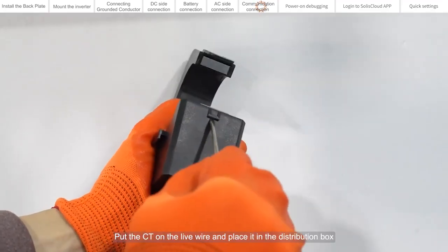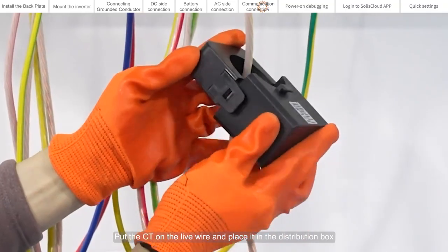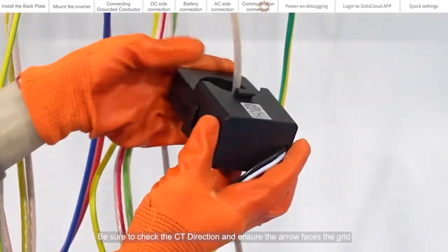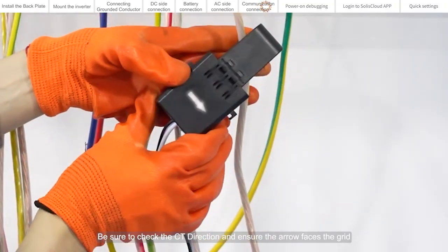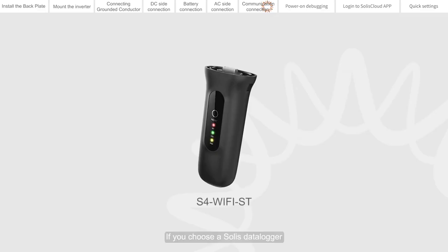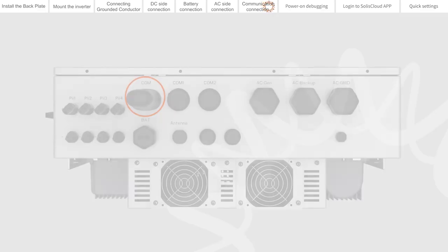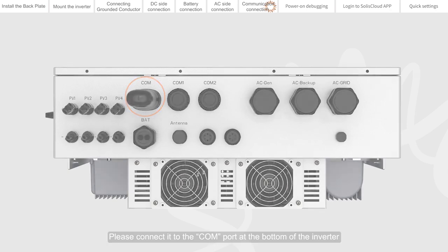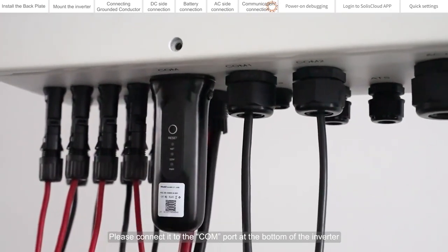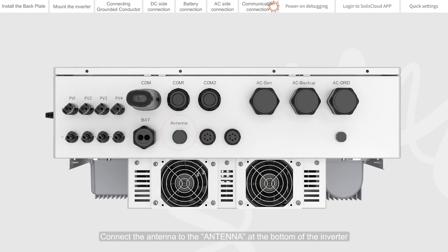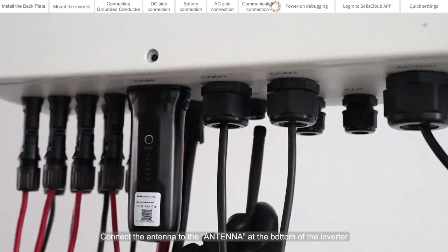Put the CT on the live wire and place it in the distribution box. Be sure to check the CT direction and ensure the arrow faces the grid. If you choose a Solis data logger, please connect it to the COM port at the bottom of the inverter. Connect the antenna to the antenna port at the bottom of the inverter.